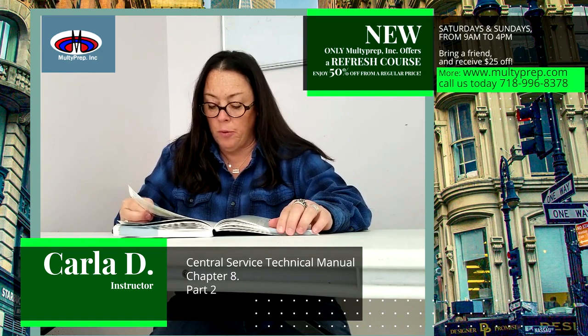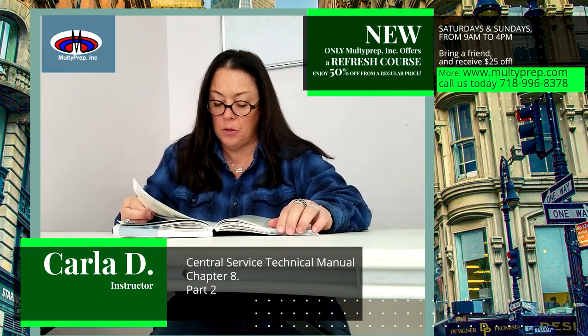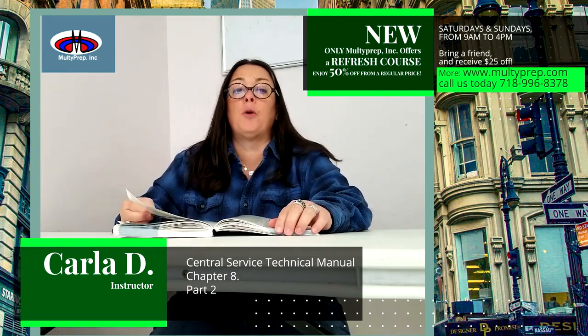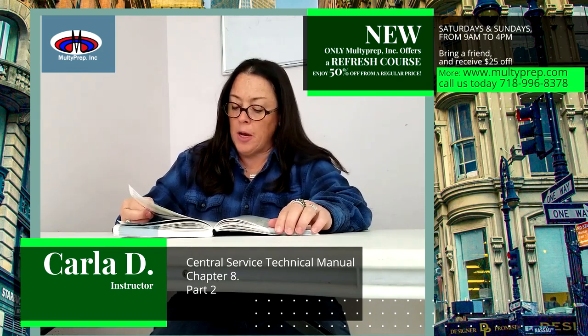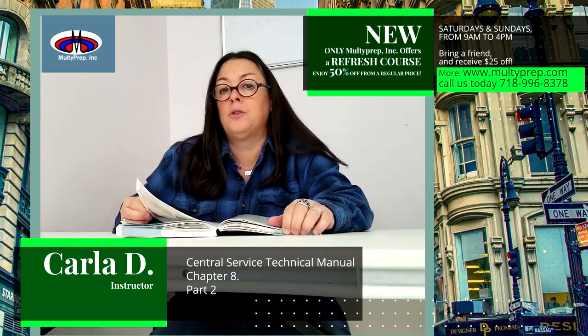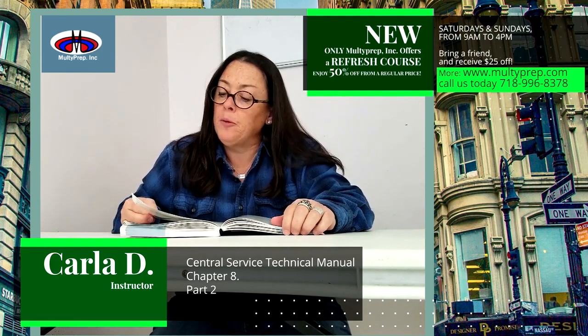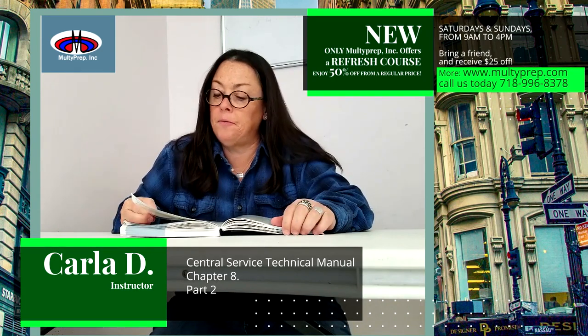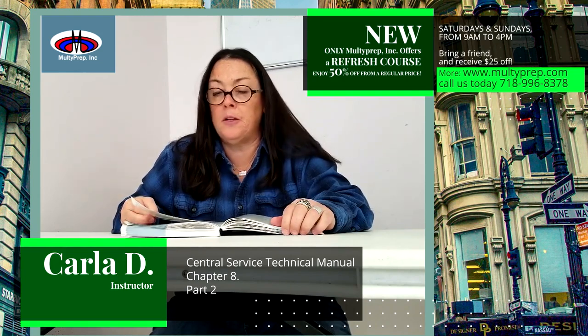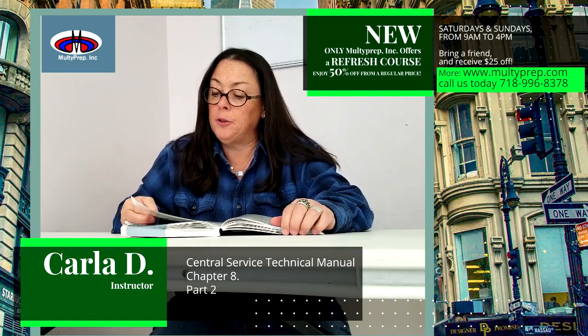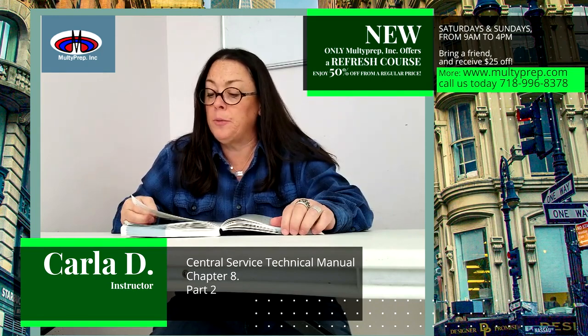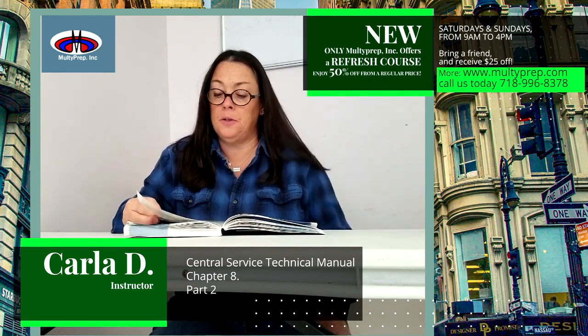Most stain and rust removers are acid-based compounds, which is 0 to 6.9 pH, that react with minerals and iron on the instruments. They remove mineral and detergent buildup, leaving the surface bright and shiny, and the instruments moving freely. Because these chemicals are acid-based, the IFU must be carefully followed to prevent instrument damage. After using a stain remover, the instruments should be re-cleaned.